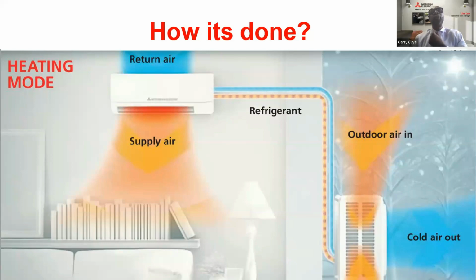Now, air source heat pump technology, how does it work, right? It's pretty much the reverse of your air conditioning unit. For those of us who are not quite familiar with the technology itself, if you have stood by the outdoor unit of your air conditioning system during the summer, you feel quite a lot of warm air coming out of it. What it's doing is extracting the heat from within the home and dumping it outside. The reverse happens during the winter. The heat pump reverses its cycle, where now it takes the heat from outside and dumps it inside. So the discharge air that is coming into your home is going to be warm air, and the outside air that's being absorbed is cold.